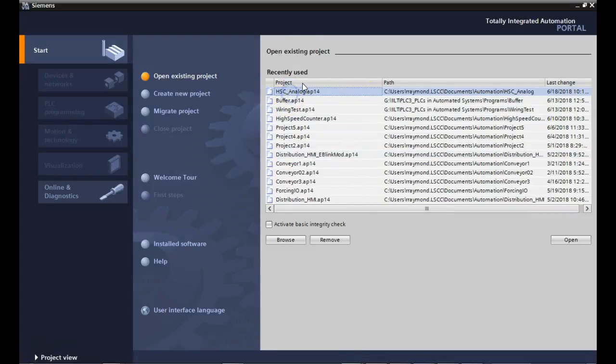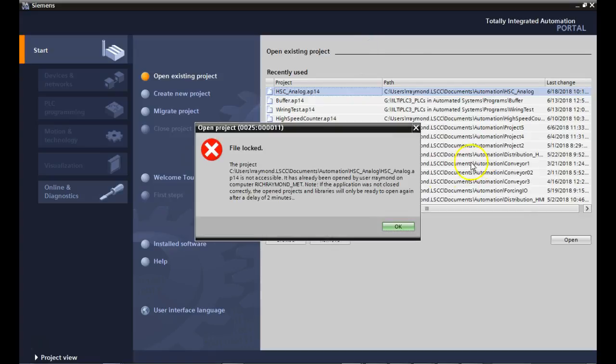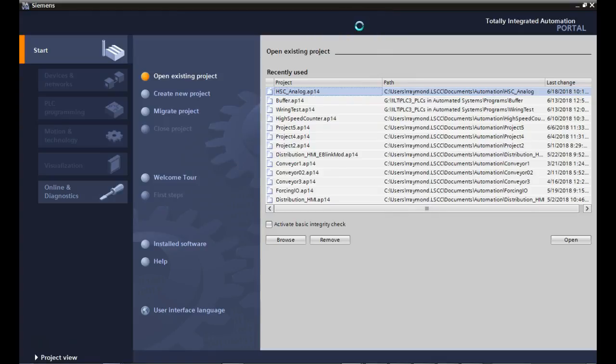So I'm playing around with analog inputs and high-speed counters. I'll try to show you all that before we get here. The counters that we use in intro to PLCs are software counters, which means they're implemented by programs. The advantage that hardware has over software is hardware is always a lot faster, because it's done electronically. If you ever looked at the machine language program that did counting, it's going to be a pretty complicated program, and it takes probably milliseconds to actually run through a counter. There's a lot of applications, especially on high-speed encoders, where we use them to establish position and speed, where those counters just can't keep up with that.